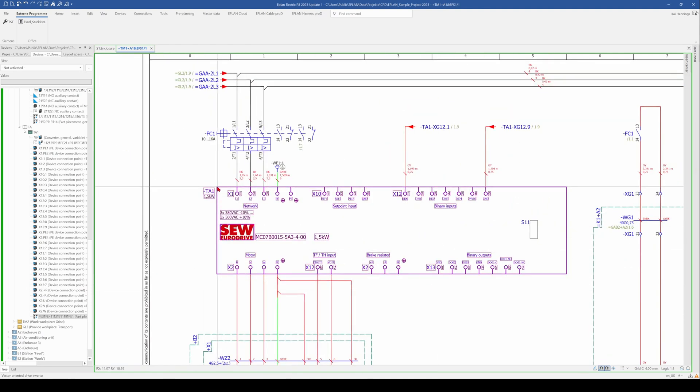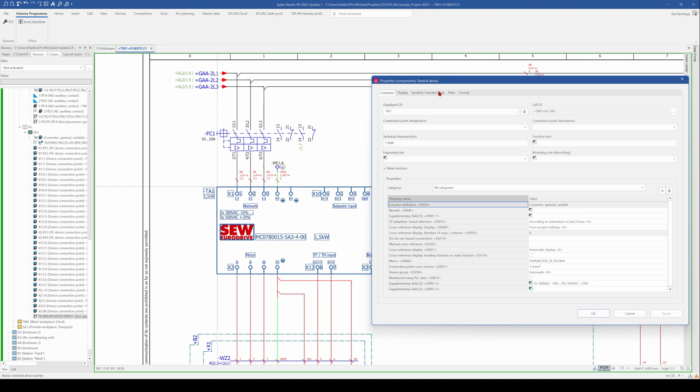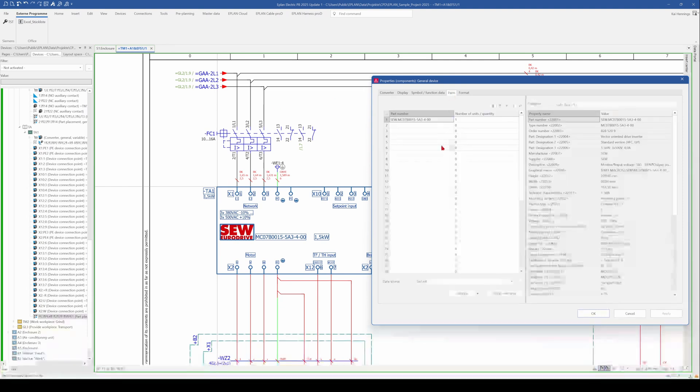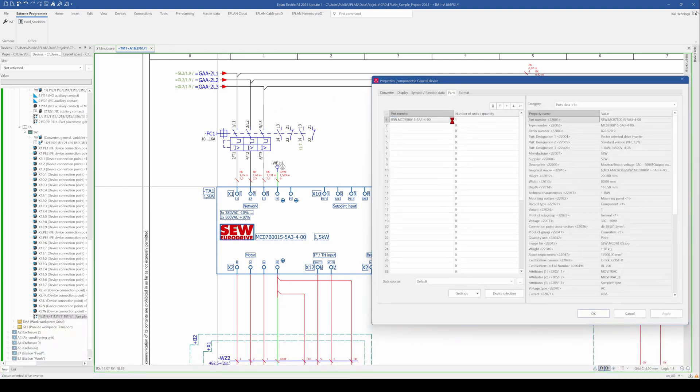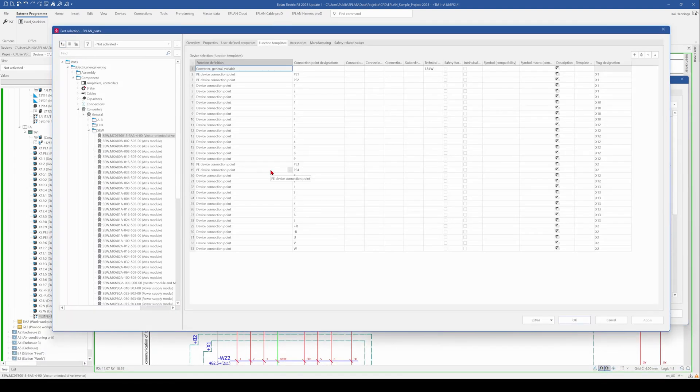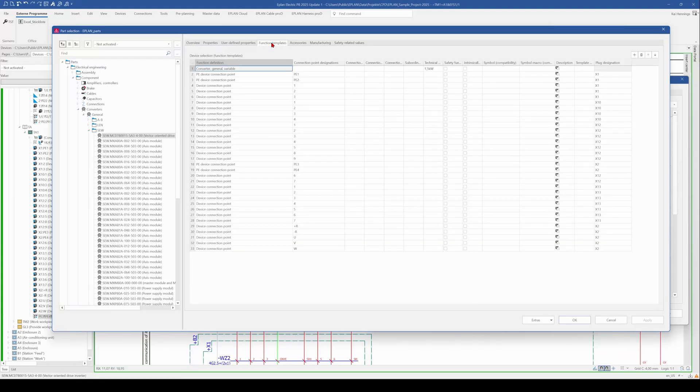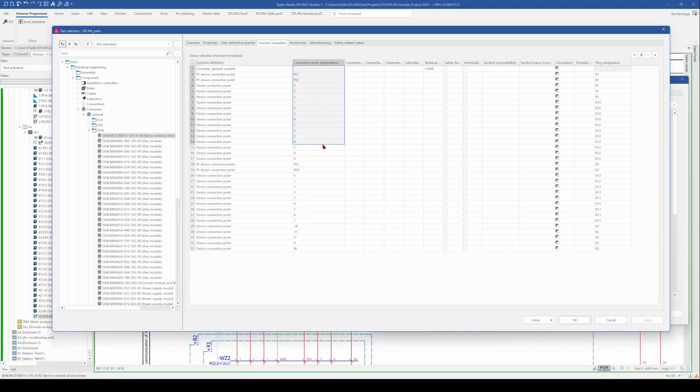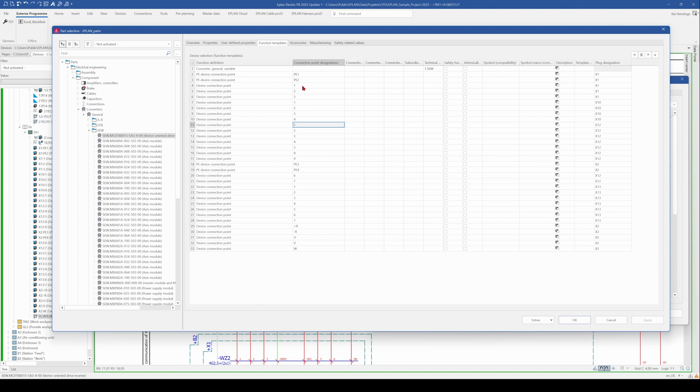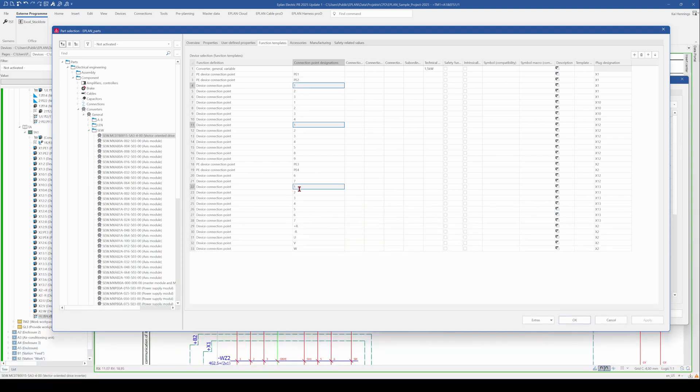And now let's have a look in the function template. So when we go here to the device on the tab parts, jump into the parts management. And here we go directly to the tab function template. You can see that the connection point designations are defined here. And for instance, you have the connection point designation 1 several times. And this is something that would create a fault message in ePlan.